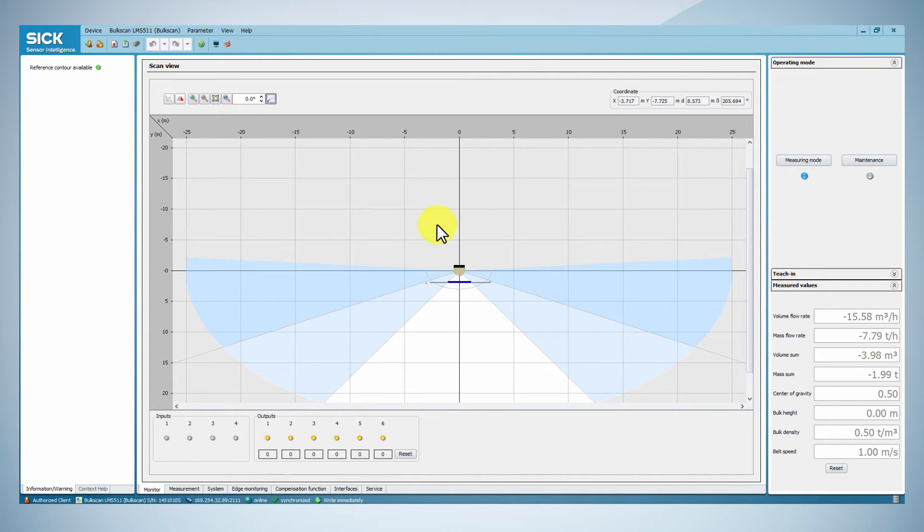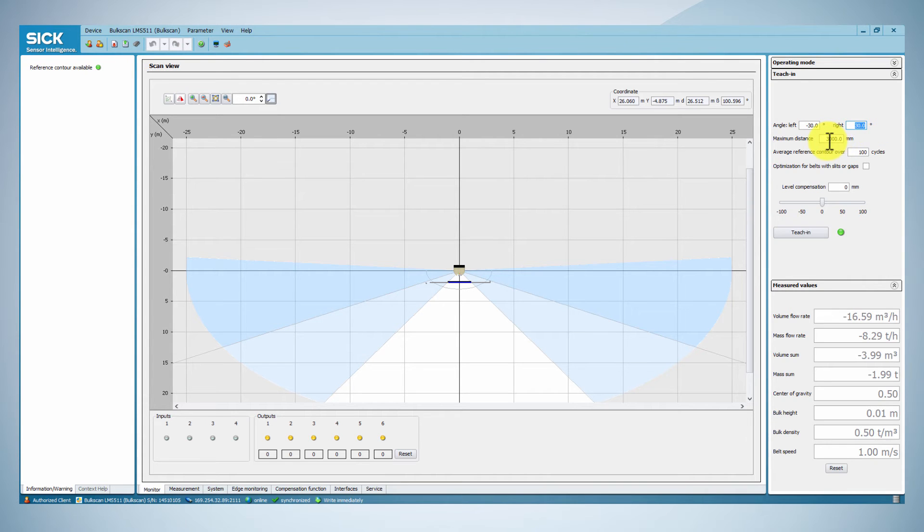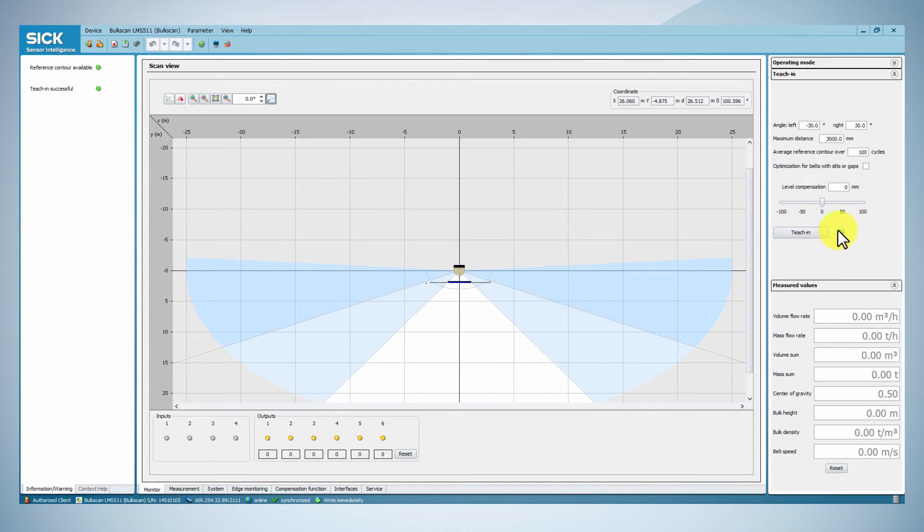We will start the commissioning by teaching him the reference contour. Set the left and right angles such that the maximum possible conveyor belt width can be acquired. Consequently, set the maximum distance and then click on the teaching button. As soon as the teaching is finished, the green indication appears in the top left box.